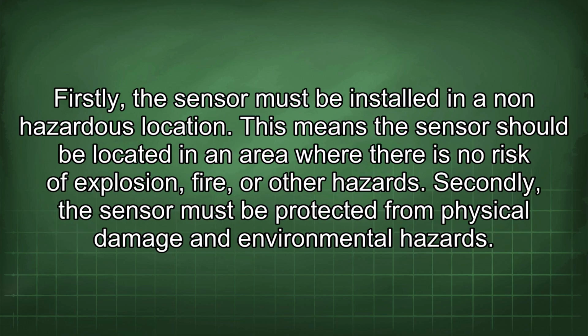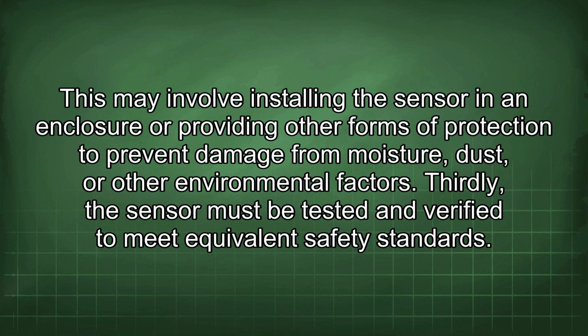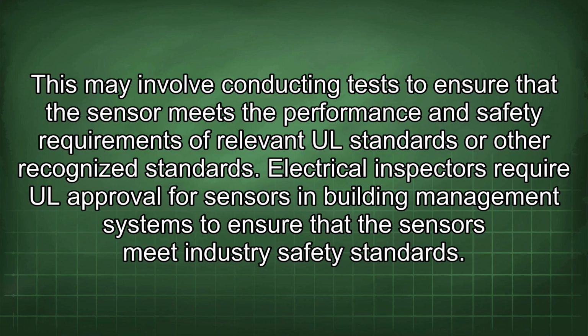Firstly, the sensor must be installed in a non-hazardous location. This means the sensor should be located in an area where there is no risk of explosion, fire, or other hazards. Secondly, the sensor must be protected from physical damage and environmental hazards. This may involve installing the sensor in an enclosure or providing other forms of protection to prevent damage from moisture, dust, or other environmental factors. Thirdly, the sensor must be tested and verified to meet equivalent safety standards. This may involve conducting tests to ensure that the sensor meets the performance and safety requirements of relevant UL standards or other recognized standards.